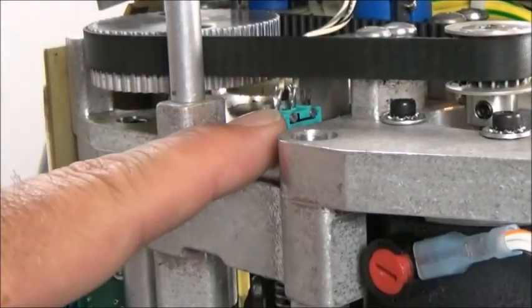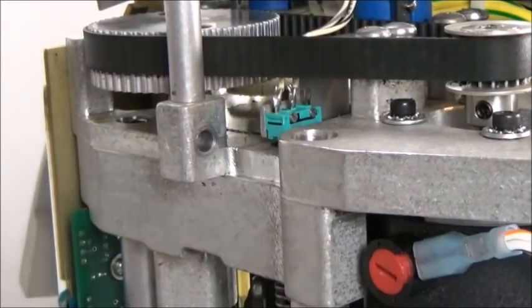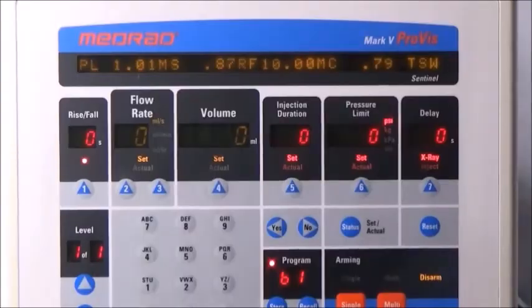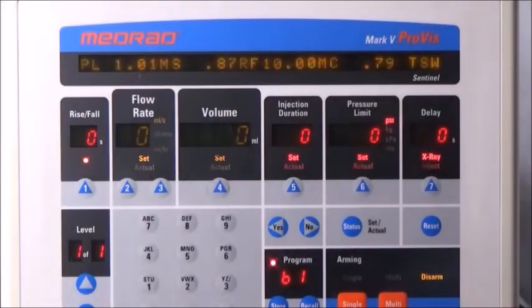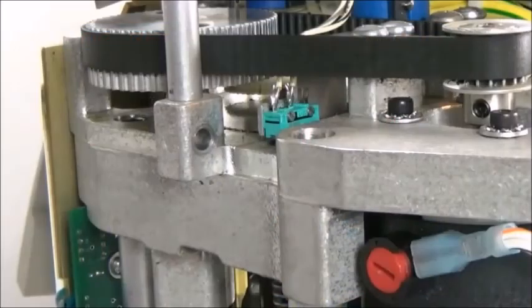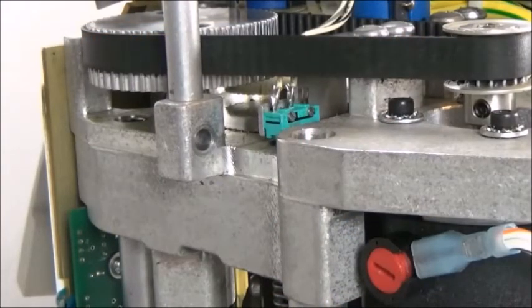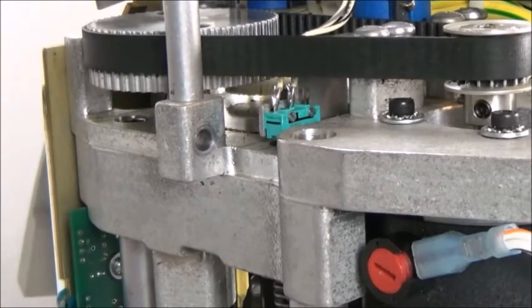This step ensures the proper operation of the MS Microswitch. With the two plates still touching, observe that TSW is showing on the right side of the display. This indicates that the small blue MS Microswitch is operating properly when it is opened. This microswitch is what electronically stops the injection if the two plates should ever come in contact with each other.